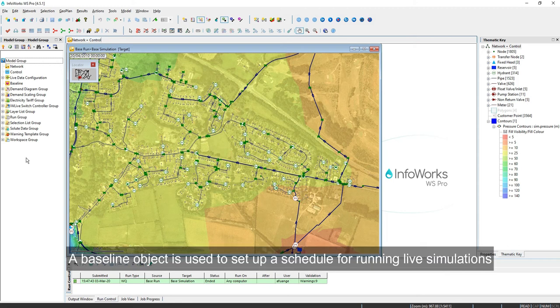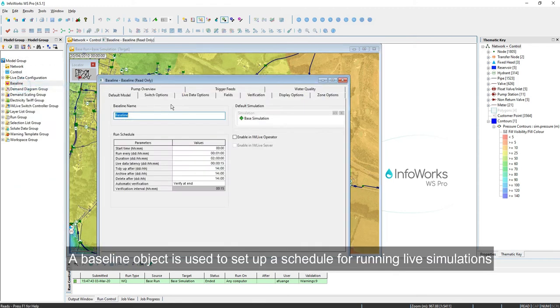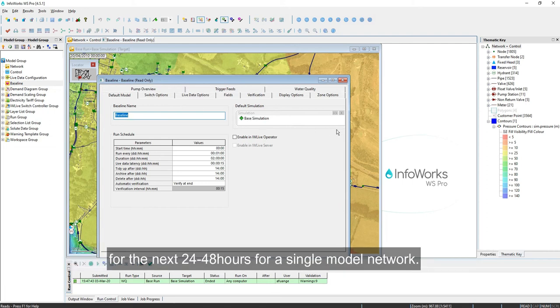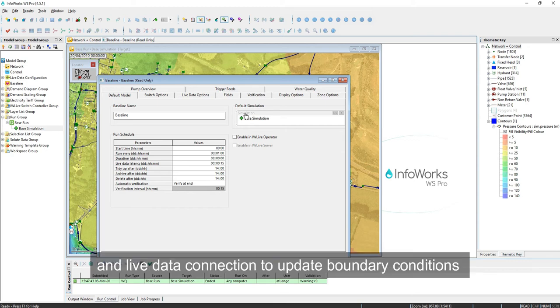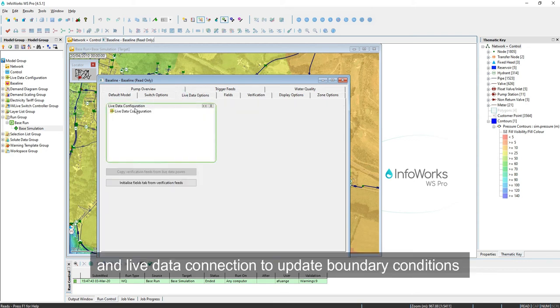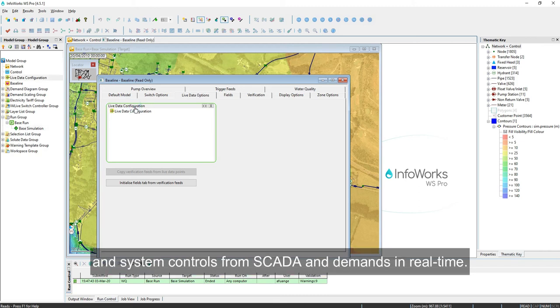A baseline object is used to set up a schedule for running live simulations for the next 24 to 48 hours for a single model network. It includes a base simulation which provides default setup data and a live data connection to update boundary conditions, system controls from SCADA, and demands in real-time.